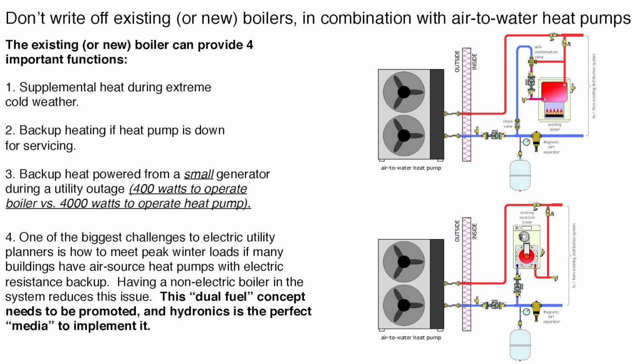That's resiliency, okay? And the other thing is having a boiler in a system, having what we call a dual fuel system, it opens the opportunity for what are going to be very creative electrical utility rates. You're going to see real-time pricing, off-peak rates. I just talked to some people up in Maine. They have so much wind generation in northern Maine, there's actually times when they were paying customers to take the electricity. They had negative electric rates. But even without the negative sign, if you're buying electricity at 1 or 2 cents a kilowatt hour, that's when you want to run the heat pump. If you're paying 25 cents a kilowatt hour on peak, that's when you want to run the boiler. So it opens the opportunity for a system like this to integrate with what the utilities are likely to do. Utilities are trying to shift the load from peak to off-peak periods. And those rate structures need to have some kind of mechanical system that's compatible.